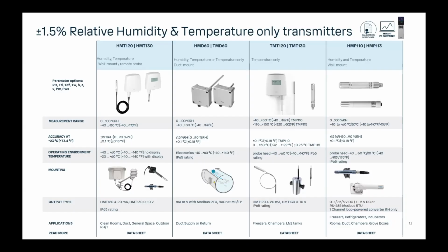And then all the way on the right, I'll skip over there. That's actually the HMP 110 and HMP 113 probe. That's the probe that's specifically used with the HMT 120. So that's a removable probe that can be calibrated separately. So if you ever do need to service things and you don't want to shut down your process or pull it out of your system, you can keep spare probes on hand that are calibrated and swap them into your HMT 120, and then send that one out for calibration or calibrate it yourself while the other one is in place taking measurements.